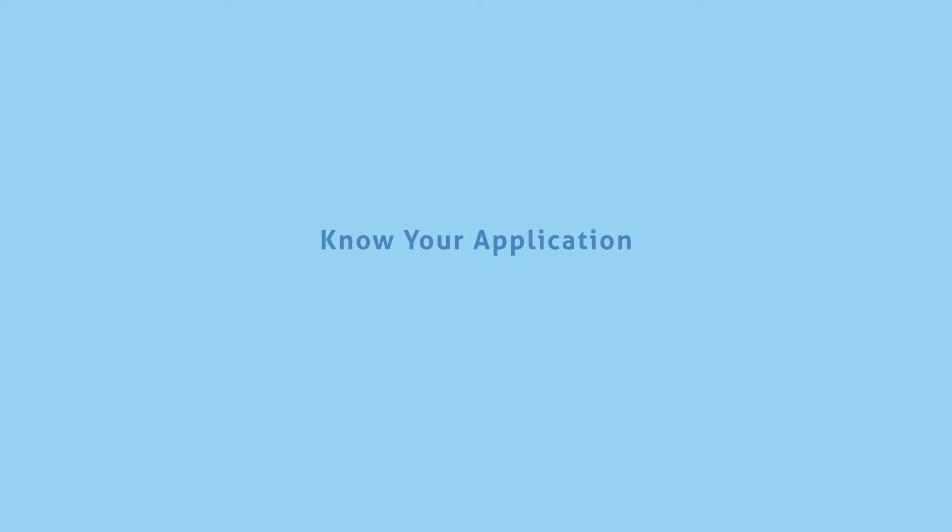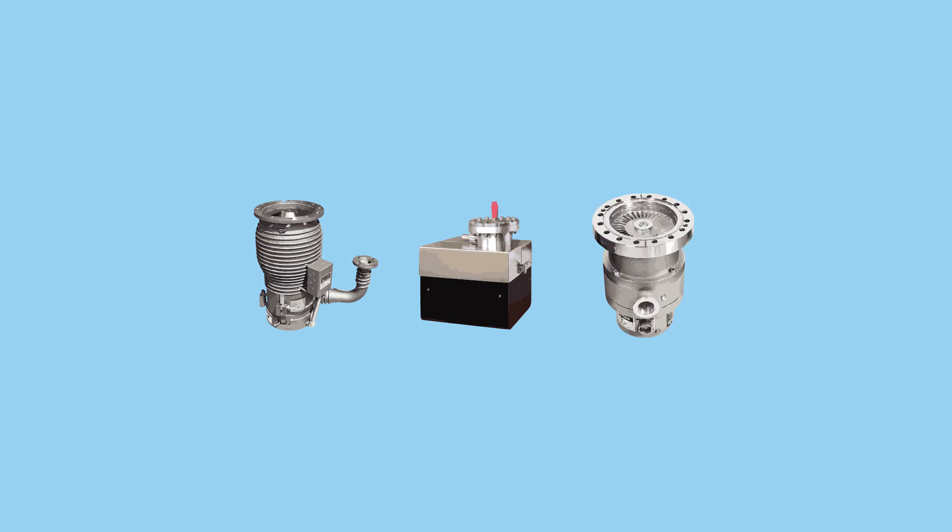Some applications require extremely deep vacuum. Atomic physics, field emission microscopy and x-ray photoelectron spectroscopy may require vacuum pressures between 10 to the minus 3 to 10 to the minus 9 millibars. For these applications, a diffusion pump, ion pump or turbo molecular pump may be the best or only choice.